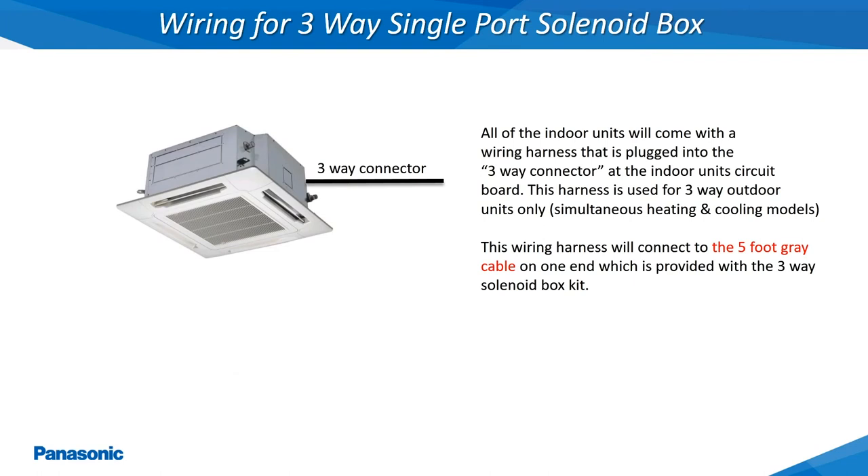All of the ECOi VRF indoor units will come shipped with a 5 conductor wiring harness already attached to the 3-way connector of the indoor unit's printed circuit board. This wiring harness is only utilized when the installed outdoor unit is a 3-way model. On the 3-way system, this wiring harness will connect to a 5 foot gray cable which then connects back to the relay box portion of the 3-way solenoid box kits.